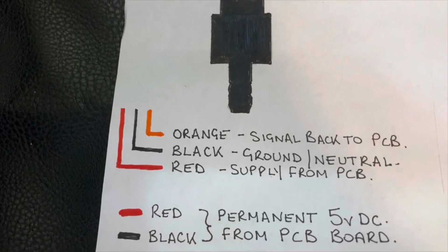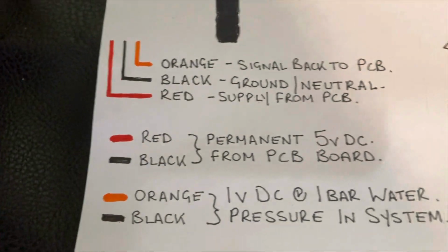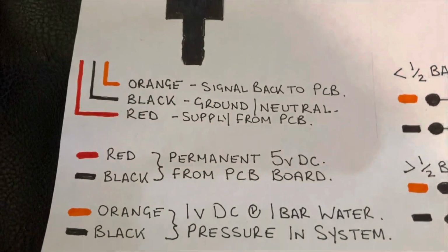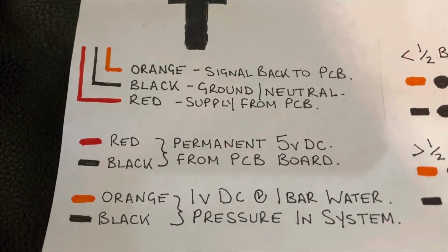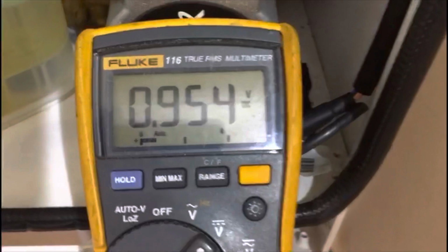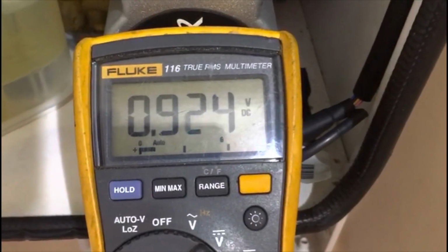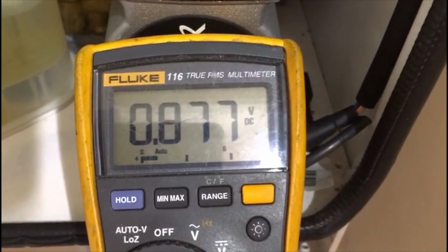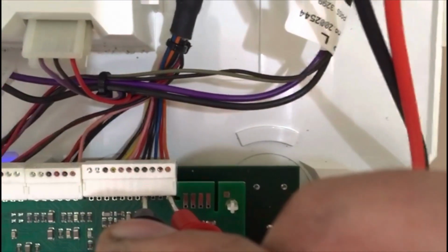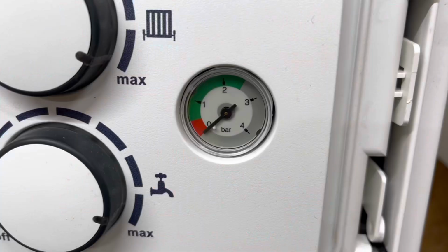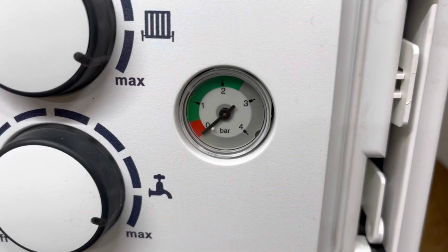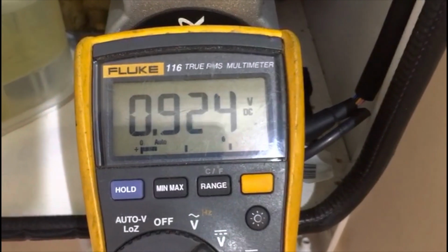Our next test is to trace the orange and black cable, and again we expect to see 1 volt DC at 1 bar of water pressure. If your pressure gauge is reading one reading and your transducer is reading another reading, it may be that your transducer is okay, but the pressure gauge may be blocked or faulty. So you'll have to determine which one is at fault. I can't really tell you how to do that, to be honest with you. That's something you must decide yourself. But we are getting the right voltage.